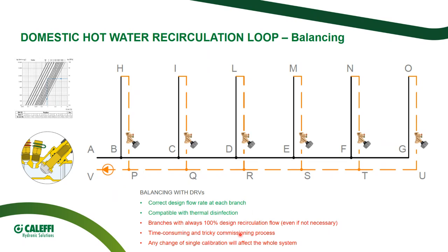Then let's start with the limit. The branches are always supplied with 100% design recirculation flow, even if this thermal power is not necessary, so they cannot grant the optimization of the thermal energy. Second, as we mentioned previously, the commissioning process might be tricky and will take a lot of time to the contractor. Sometimes it is neither done. And the change of any single calibration or the replacement of any single valve in this system will affect the setting of the whole system, so the process of commissioning and calibration has to be restarted from the beginning.